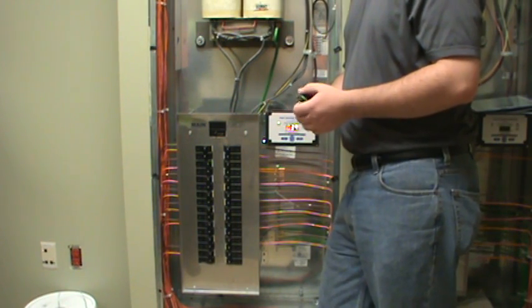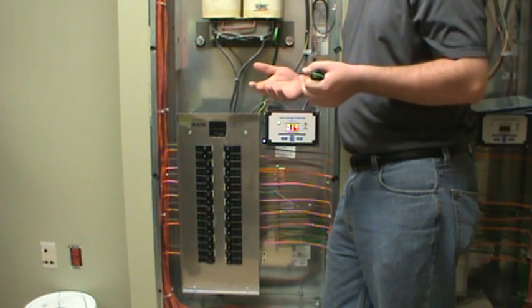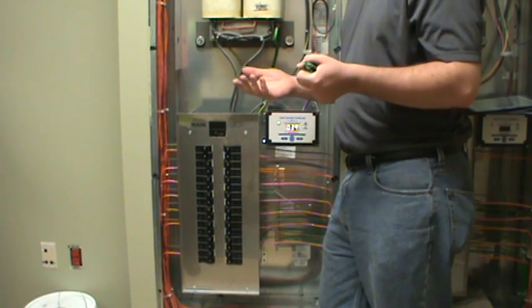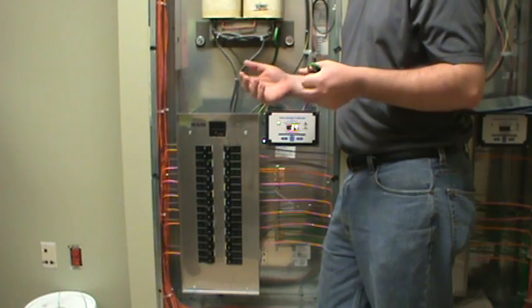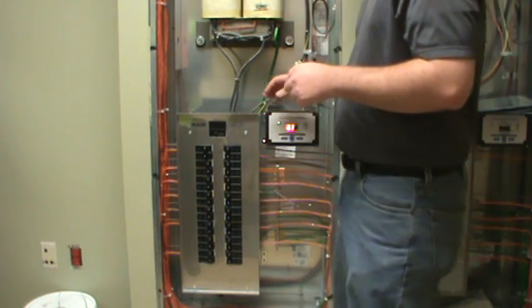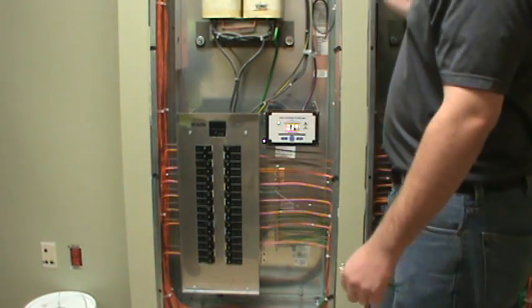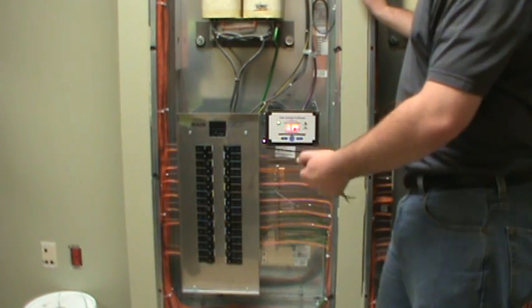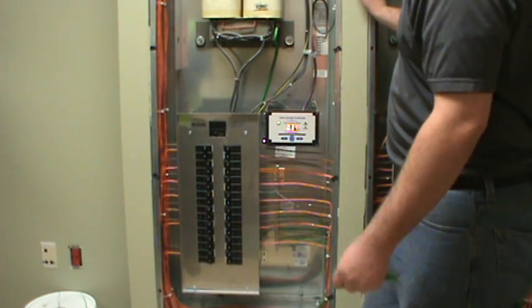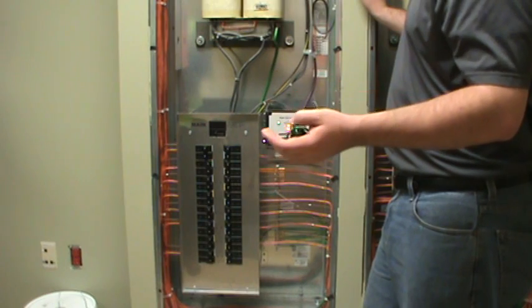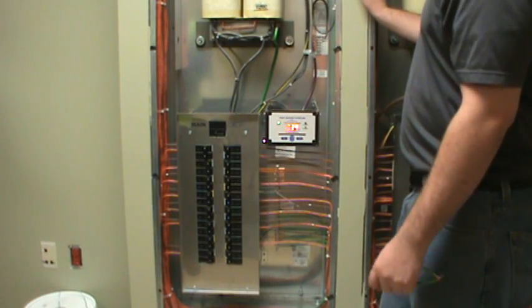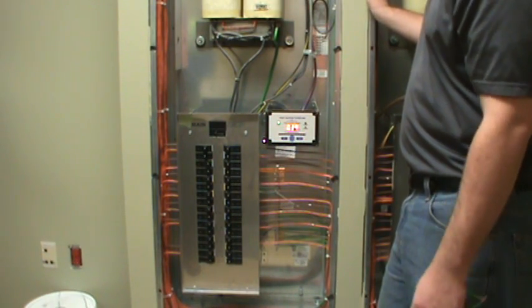It's a safety feature that if something were to be shorted with a ground fault, that would be either line, hot or neutral, shorted to ground, then the circuit won't trip, your breaker won't trip if that were to happen. And also there won't be a dangerous short, a dangerous spark. So those are two main functions of our panel here.